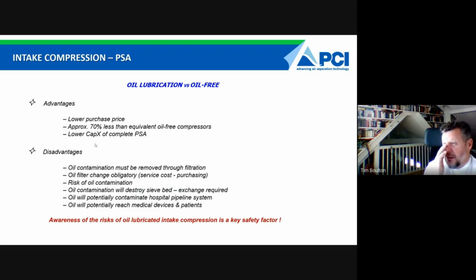I've personally seen oil in hospital pipeline systems. So it's gone straight through the system and it's gone into the hospital pipeline and will ultimately reach the patient, which is not what you want to do. As it says here, oil contamination is a big risk. It'll destroy your sieve bed. If it gets through, it will potentially contaminate the hospital pipeline system. And the worst of all, it will potentially reach your medical devices, your ventilators, your anesthesia machines, and maybe even the patient.